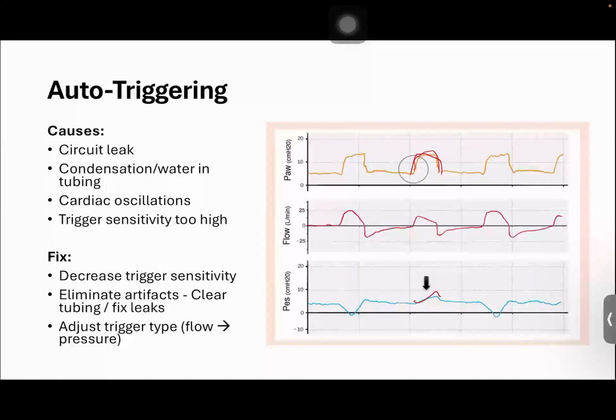Another thing is when the patient has cardiac oscillation, especially in a high cardiac output state, where the cardiac oscillation can be misinterpreted as a respiratory effort and cause a ventilator breath. Also, if we set a higher sensitivity level, for example a flow trigger of 1 liter per minute, even the slightest flow change will induce a ventilator breath.